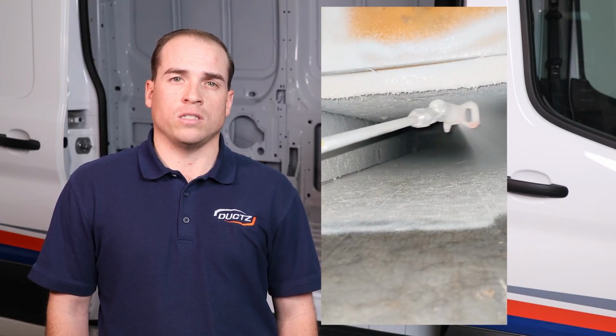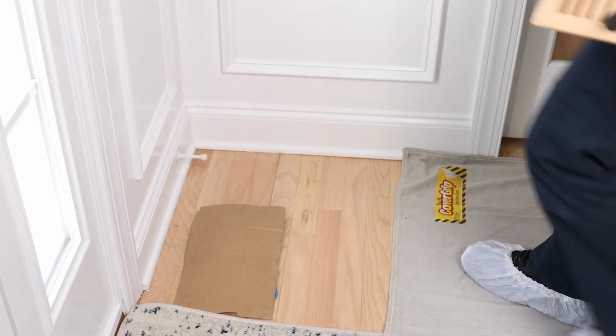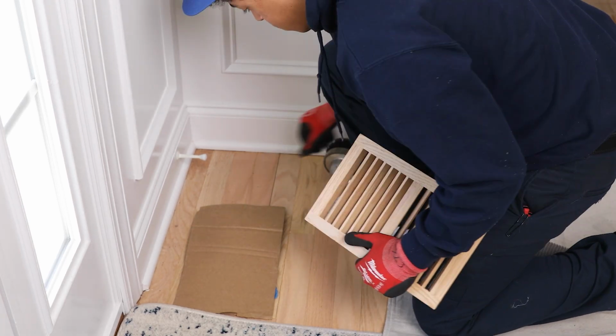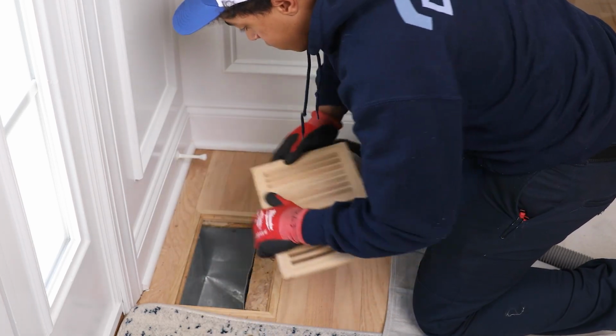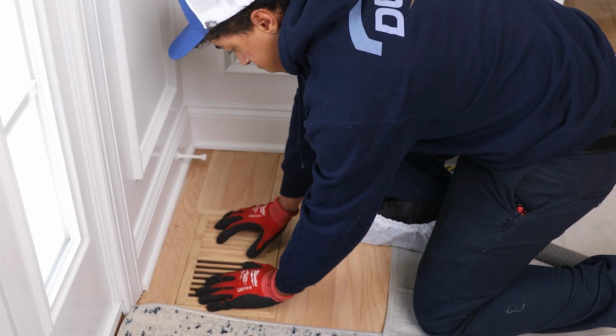To prevent this from happening, after we clean the ductwork, we use a coating product called Fiberlock IAQ 8000, which is a coating made specifically for coating insulation in HVAC systems. We apply it with a paint sprayer and let it dry before turning on the system. Once the cleaning and coating process is complete, all that's left for us to do is put everything back the way we found it.